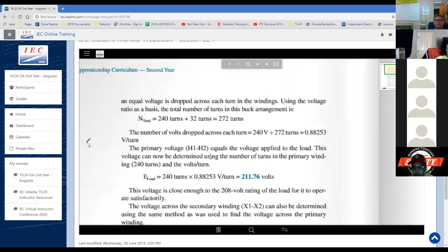We also check it by the windings. So there's 240 turns plus 32 turns is 272 turns. The number of volts dropped across each turn: you have to divide 240 by that number of turns, and you get a number, 0.88253, right? So that primary voltage, H1 to H2, equals the voltage applied to the load.